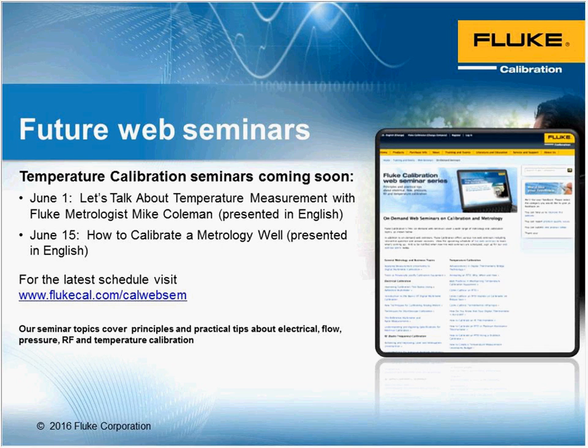This is the same with your units under test and a reference. There are different grades of PRTs and types and how they were calibrated, which will give various uncertainties based on the combination of the probe, the readout, and the heat source. So you would just want to do your homework, exploring the temperature range that you need versus the overall uncertainty that you're trying to adhere to, and then build around that.